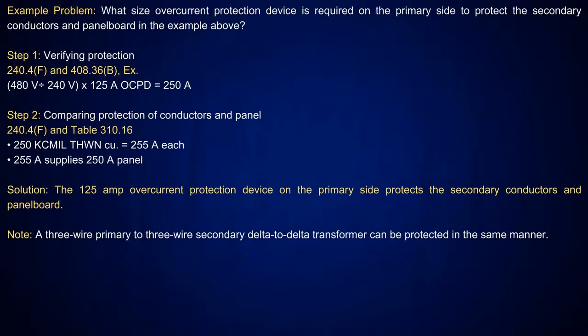All right. Now, looking at this one: what size overcurrent device is required on the primary side to protect the conductors and panel board? We had an example we were showing here, but this is very simple. I'm showing a transformer here, and all I'm going to do is, I had a 480 volt primary, 240 volt secondary with a 125 amp overcurrent device upstream. So we were just showing here how to do this calculation, and you do that. That gives you 250 amps. So I was going to size the conductors on that to protect the secondary conductors and the panel board it was going down to.